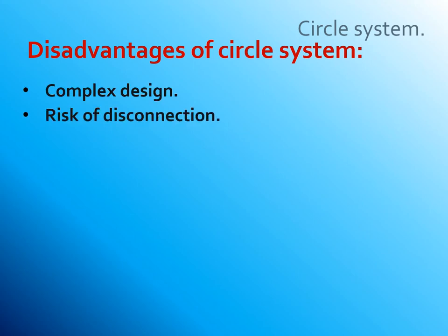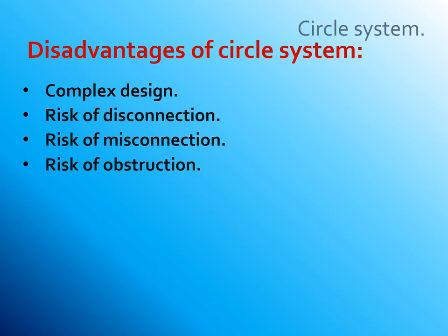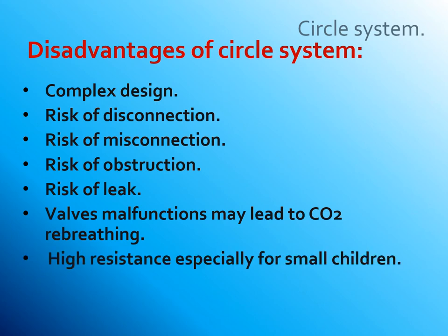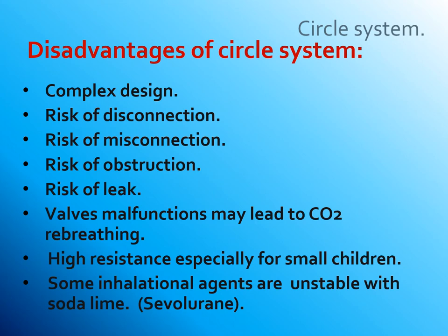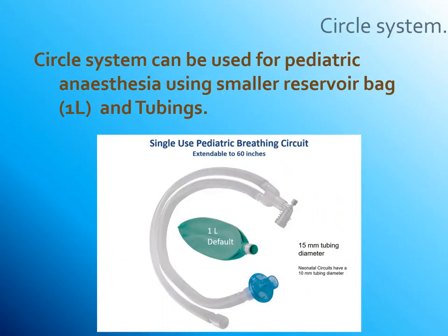Disadvantages of the circle system: complex design, risk of disconnection, risk of misconnection, obstruction, risk of leak, valve malfunction, and high resistance — especially for small children. Some inhalation agents are unsuitable with soda lime, such as sevoflurane, which may produce a toxic mixture through chemical reaction. The circle system can be adapted for pediatric anesthesia using a small one-liter reservoir bag and smaller tubing.